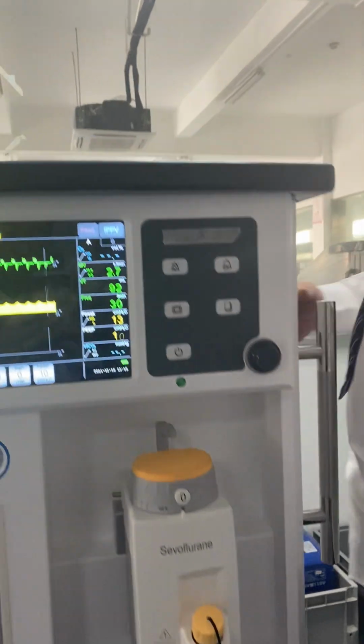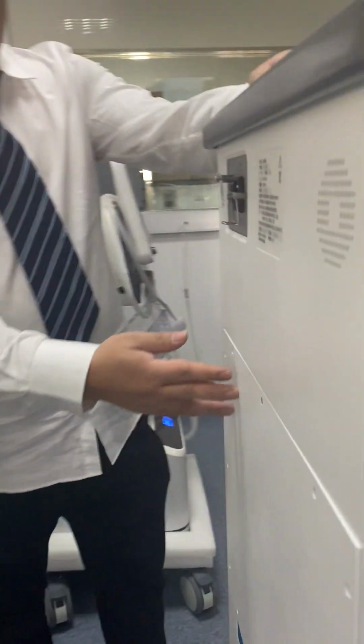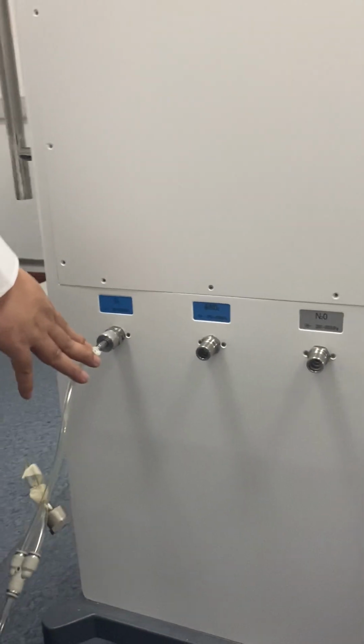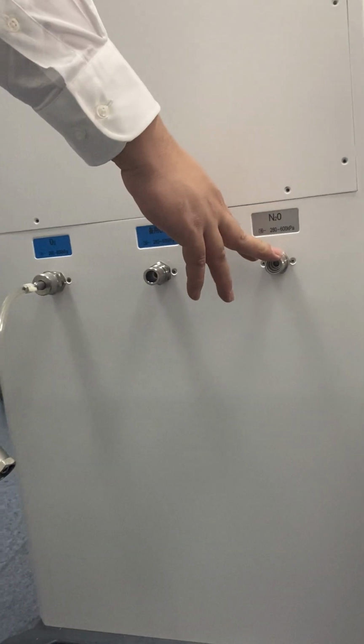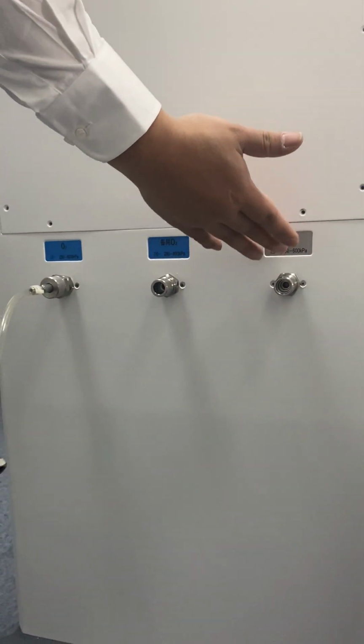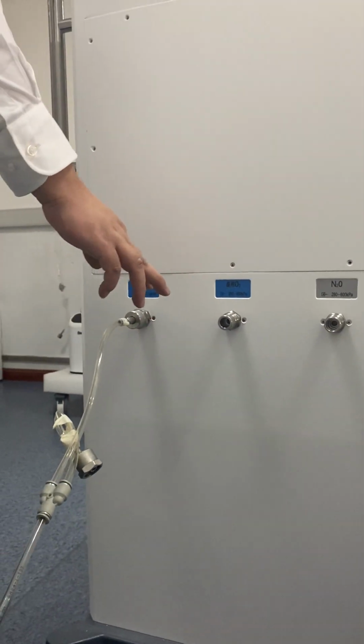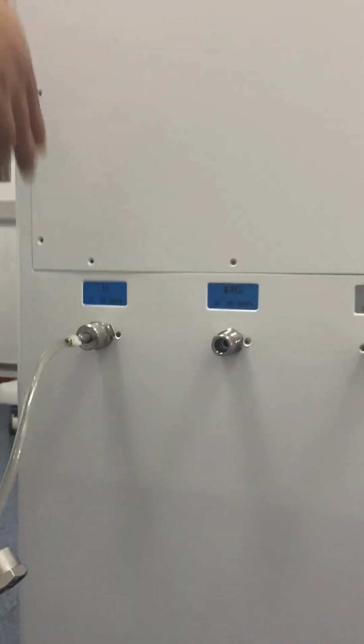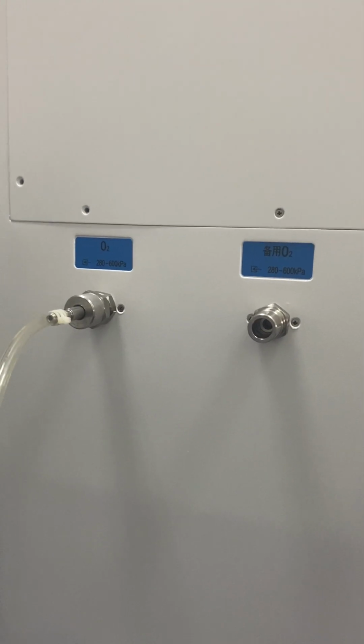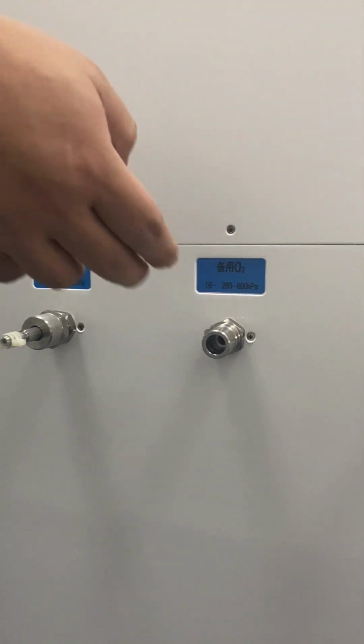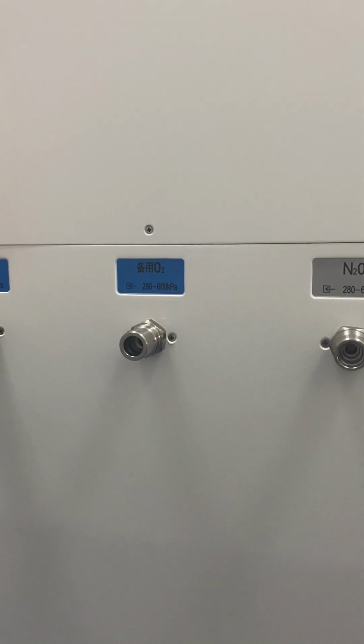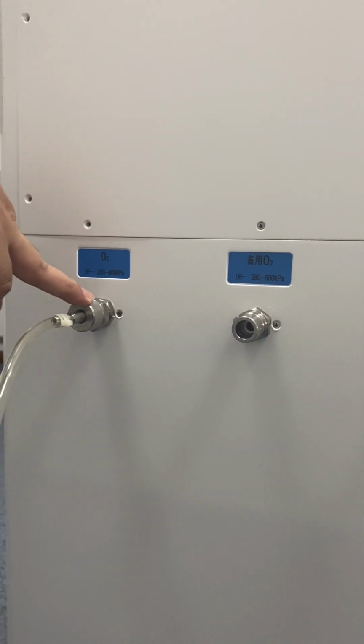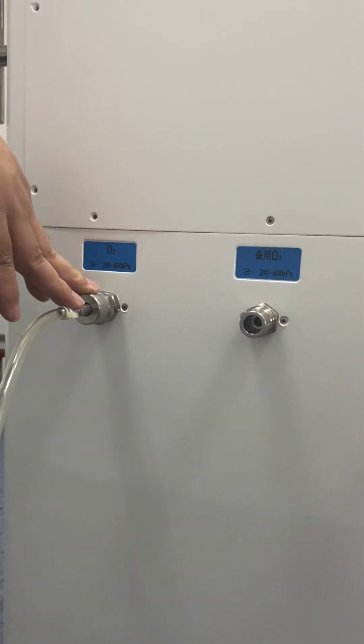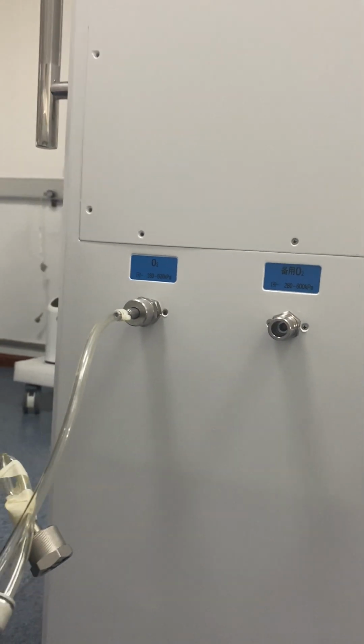The last part is here on the back side of the anesthesia machine. We will connect the oxygen source and also connect the nitrous oxide, or for this machine you can choose to change the nitrous oxide to air. Why do we have two oxygen ports? Because you may have both a central oxygen supply and an oxygen cylinder, so you can connect the oxygen cylinder from here and the central oxygen supply from here. Then no matter which one fails, the other one will supply oxygen automatically. So it keeps things safe, because oxygen is the driving gas for this machine.